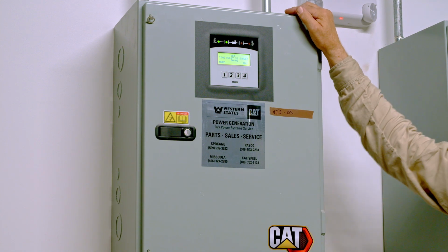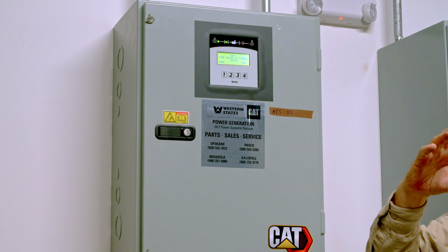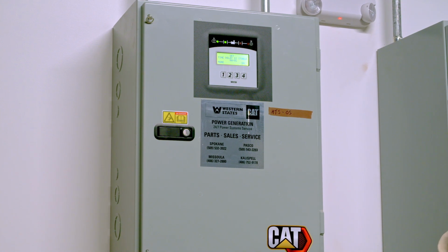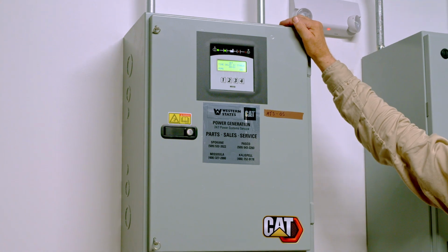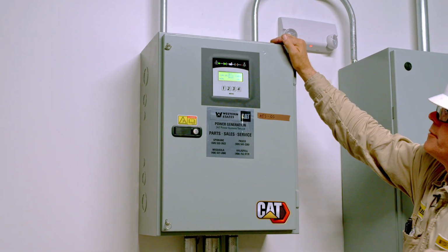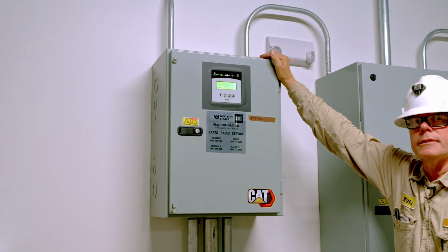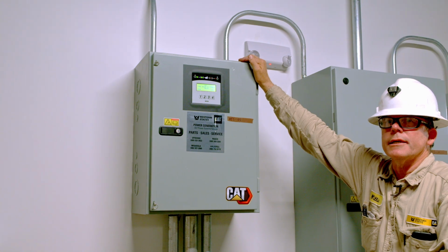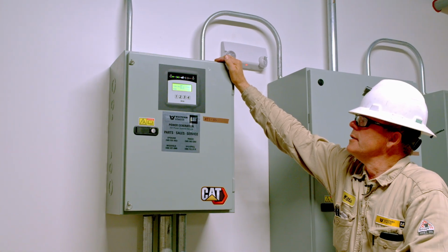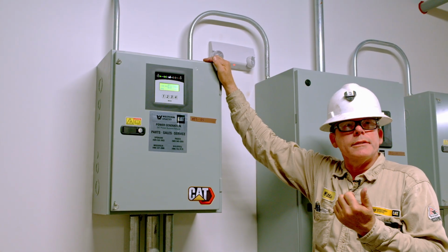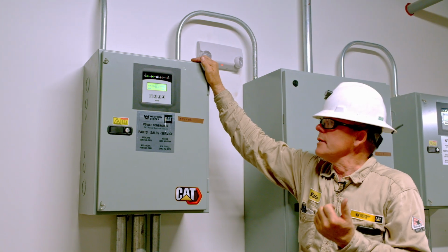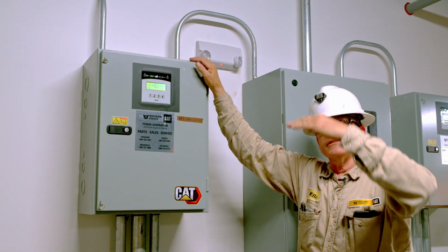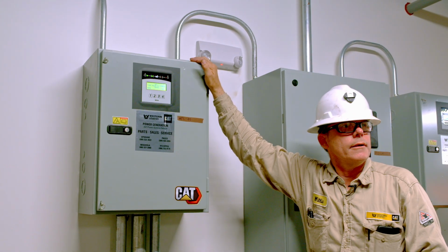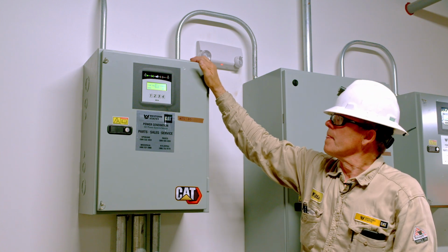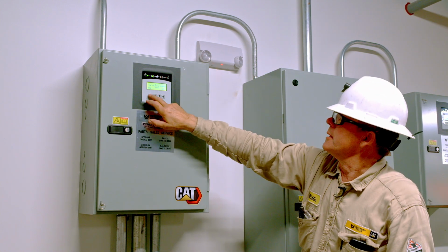in-phase monitor turned on. So it looks at both sources, and when it's within 5% or 5 degrees, it'll allow a transfer. And it has a display on the screen. We'll show that later when it's syncing. It's a passive sync, it's not an active. So the generator frequency is set at 60.1 hertz, utility is 60, so that lets it go just a little faster, so it'll run in and out of that sync window, which gives you a pretty smooth sync.